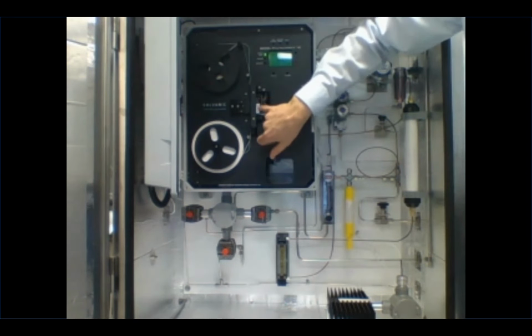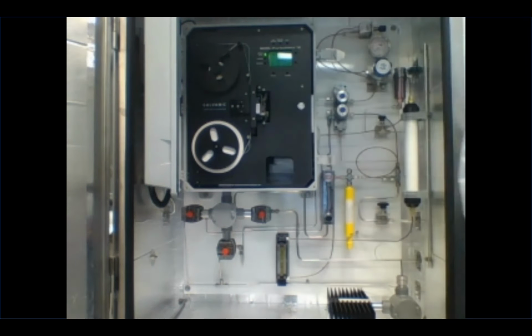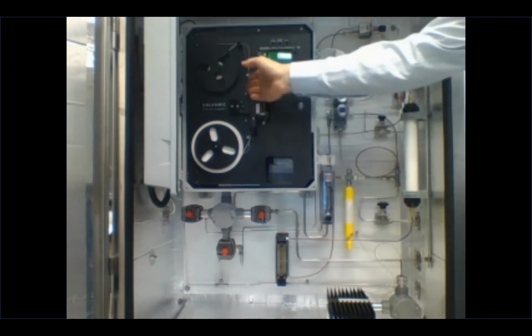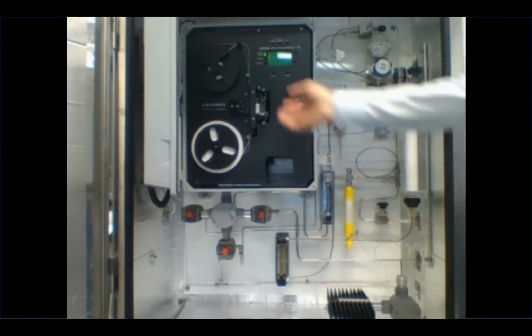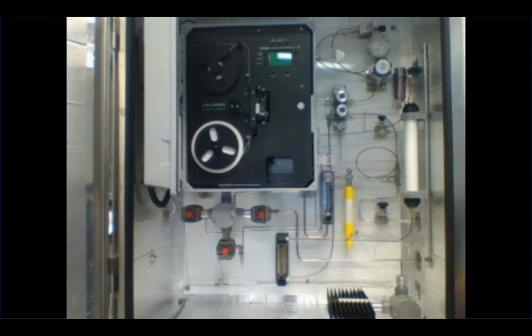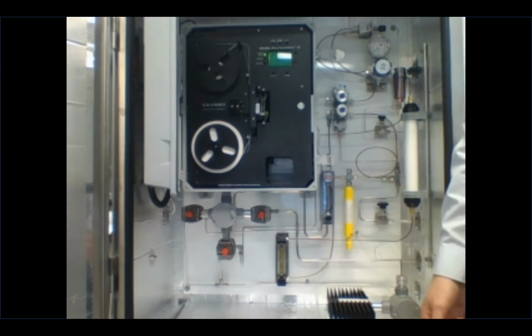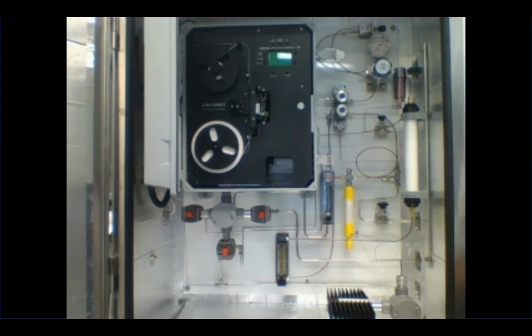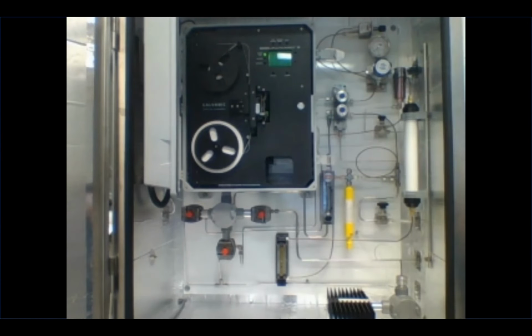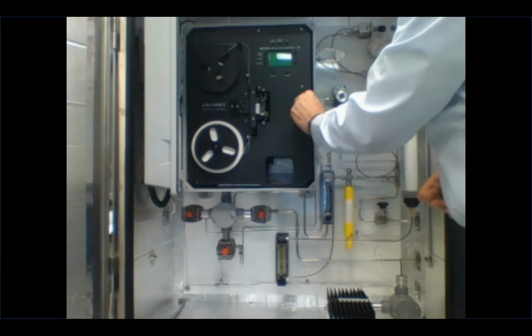That LED is illuminating the tape, and the light reflection is being read back. So that's all built into this block here. And as the arsine passes through the system, the tape will turn color, and the sensor block reads it. It kind of takes an average of the rate of staining over a period of time. Typically, the cycle times are on the order of 5 minutes. So it does an average over that 5-minute period, and then it reports a value in ppb.